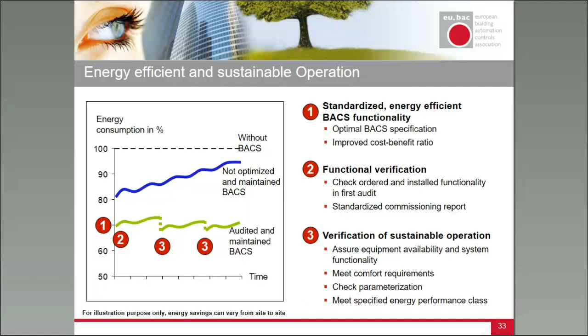Always when you take measures, these are sometimes just readjustments. A very logical example: you configure your building to be used Monday to Friday, 6 in the morning to 6 in the evening. Then one Saturday there's a special event in the building, and the facility manager goes and changes the scheduler so the building is in comfort condition for that Saturday. Then this setting is lost - it's forgotten, never reset. If you don't monitor that, from then on the building will be heated or cooled even on Saturdays when it's not used.